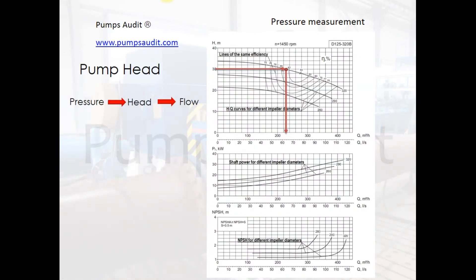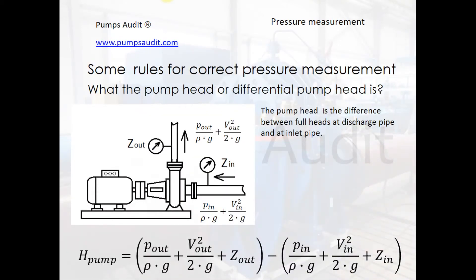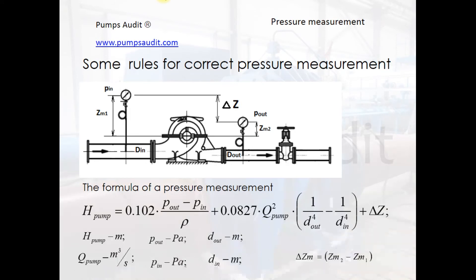This slide demonstrates: if we measure the pressure we can calculate the head, and using the pump curve we can find the position of the operating point and define flow, power, and NPSH. The pump head is the difference between the full head at the discharge pipe and the inlet. The full head is the sum of two components: velocity head and pressure head. It is also necessary to take into account the location of pressure gauges and the height difference between them. This formula can be transformed to a more applicable form using pump flow and pipe diameters.